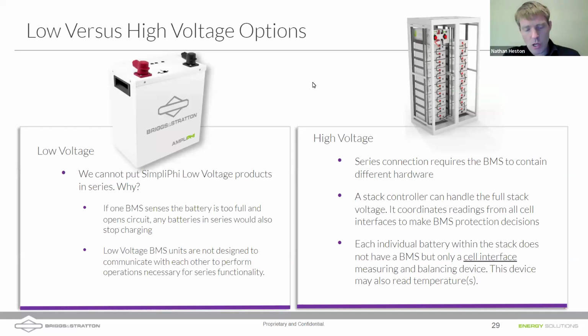If you have a battery in a large bank without communication - say 16 batteries in parallel - you often might not have any indication that a particular battery is non-functional. That argues for using communicating batteries, so you know whether a battery is charging or discharging, for example.